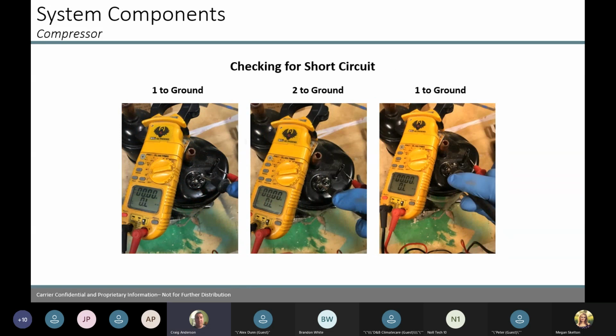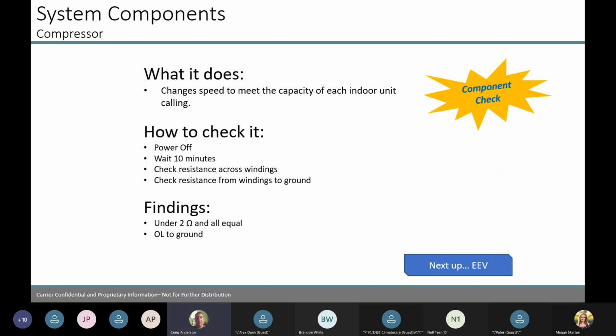So the other one, checking for a short, ground to each terminal, make sure we're OL on your board. We're just checking for a ground. So what's the compressor do? Changes the speed to meet the capacity inside the building. So this compressor is ramping up and down.